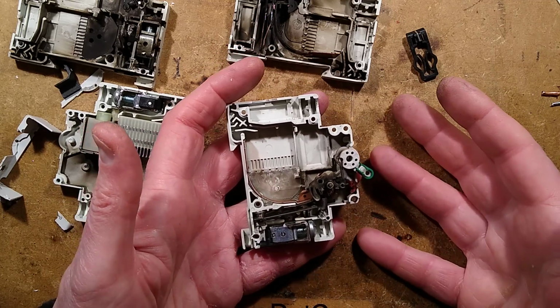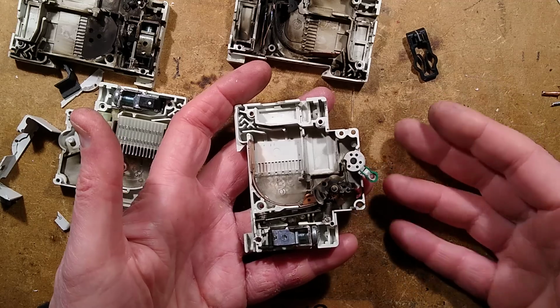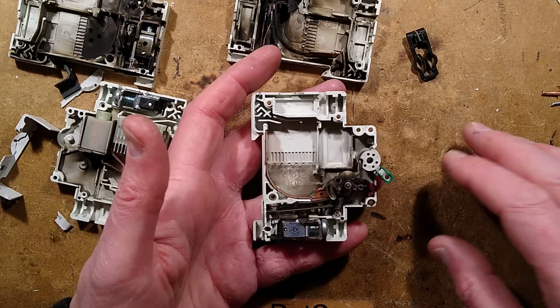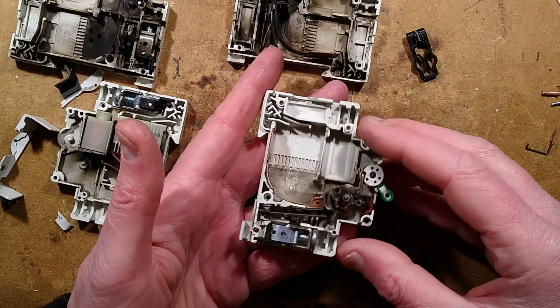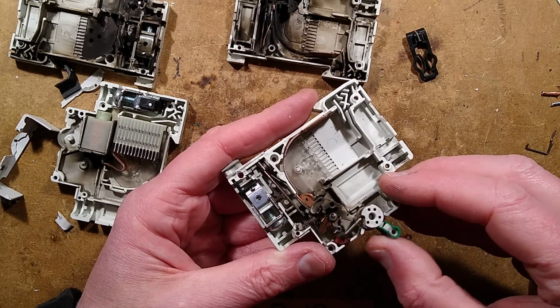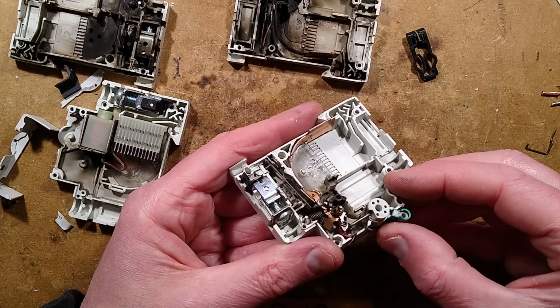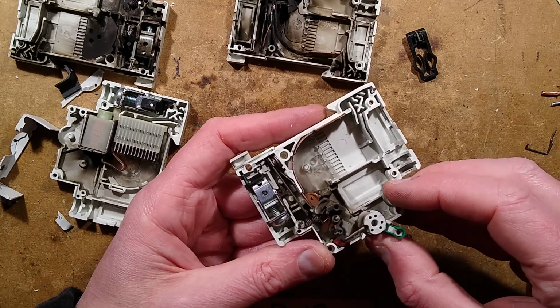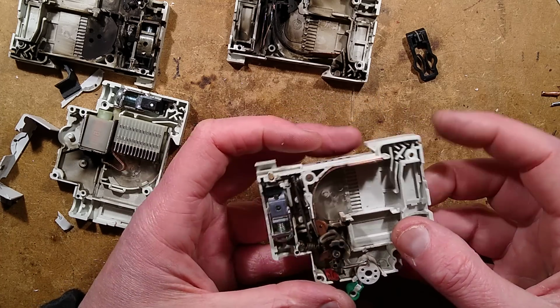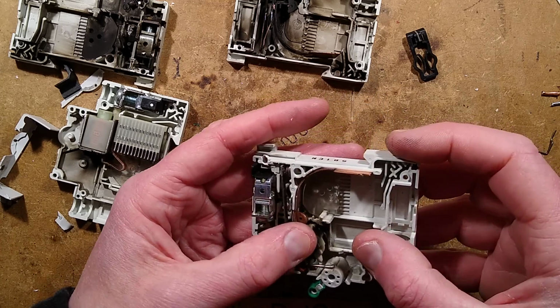Normally, if a fault was at a lower level and accessible, you could go and look for it by taking the covers off the junction boxes. But in this case it would have required a lot more work, so they just relied on occasionally resetting the breaker when it tripped. But in this instance it exceeded its number of safe operating cycles effectively.